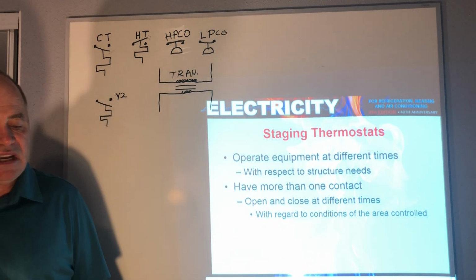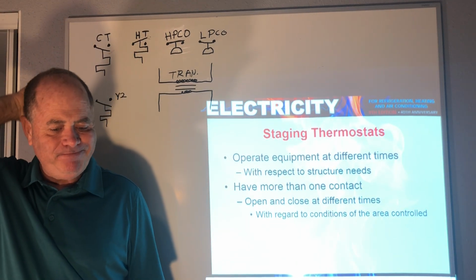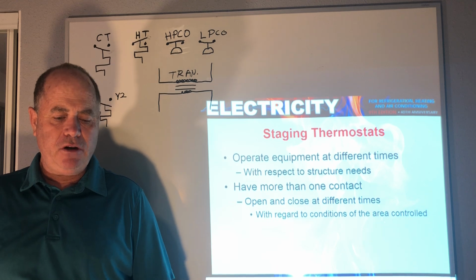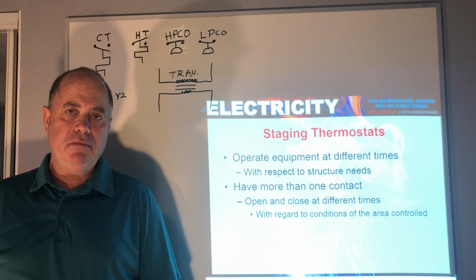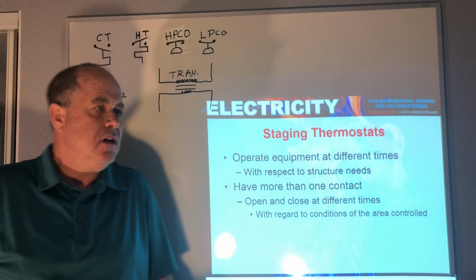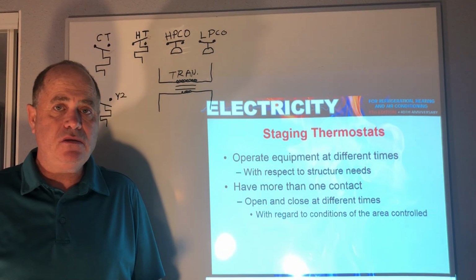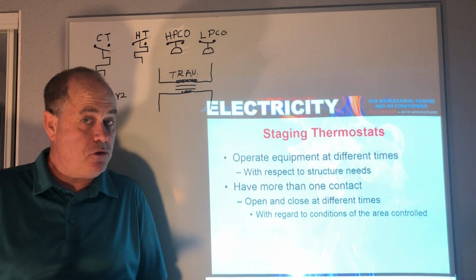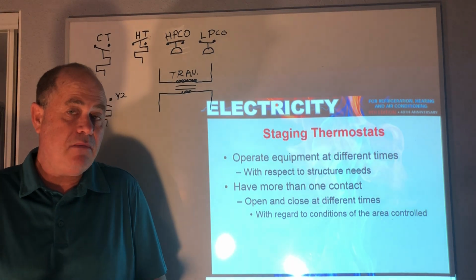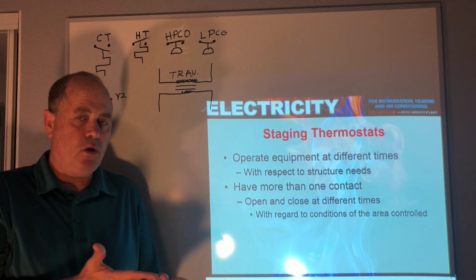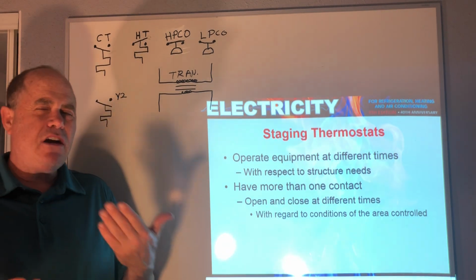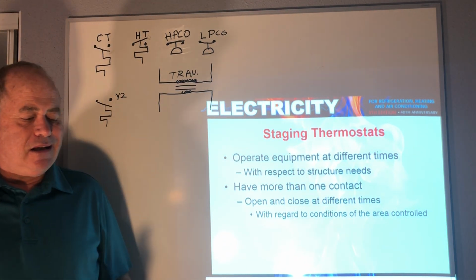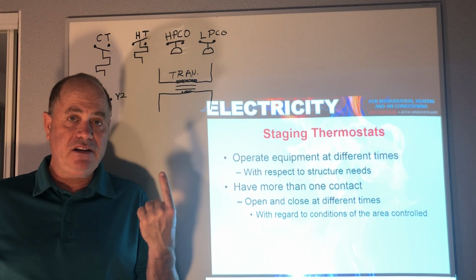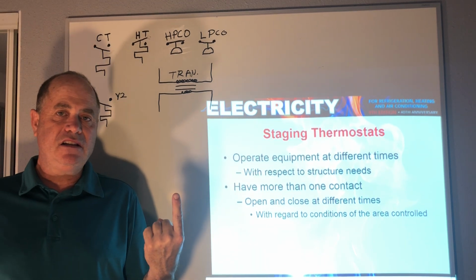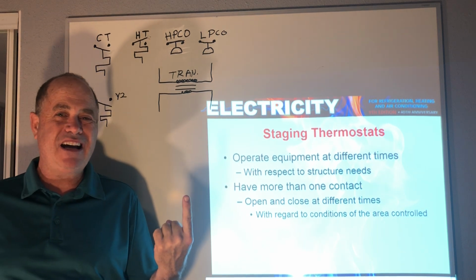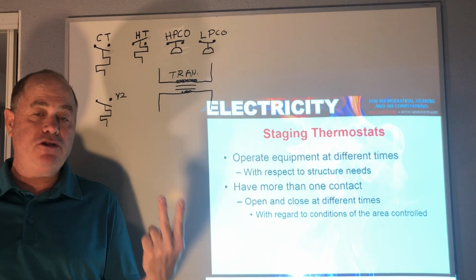Okay. Staging thermostats can operate different equipment at different times. Quite often, it might be part of a two-stage system where a thermostat is bringing on some cooling, and then if it gets a little warmer in there, it might bring on more cooling or all of the cooling. And then in modern systems, they'll rotate. So if you have a thermostat contact bring on, let's say, compressor number 1, and then it gets a little too warm in there because compressor number 1's not handling the job, then compressor number 2 comes on.